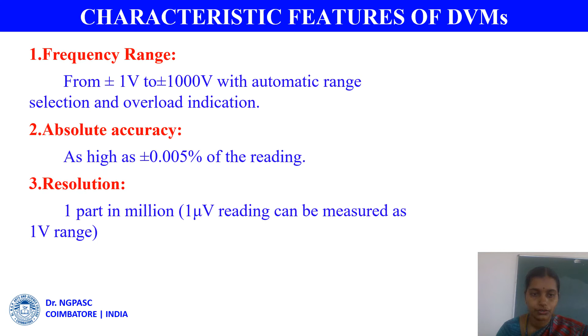The third one is resolution. 1 part in a million, that is 1 microvolt reading can be measured on 1 volt range. The fourth one is stability. The short-term stability is 0.002% of the reading for a 24-hour period and long term is 0.008% of the reading for 6 months period. Input resistance is typically 10 megaohms and input capacitance is 40 picofarad.